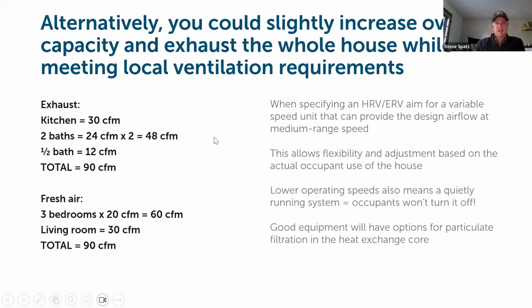So in balancing this all out to get to an actual outcome to install in the building, we're actually moving more towards that total 90 CFM requirement for the building, not taking into account the infiltration credit. So breaking that down between the exhaust and the supply side, from a design standpoint here, we're looking at providing 30 CFM of exhaust from the kitchen. When you're exhausting from a kitchen space with a balanced ventilation system, you're not using the ERV or HRV as a range hood. You still should consider having a range hood anyway that's exhausted directly to the outside. But that port for exhaust from the kitchen would be somewhere within the kitchen area, but not intended to be capturing that sort of grease-laden air coming from cooking.